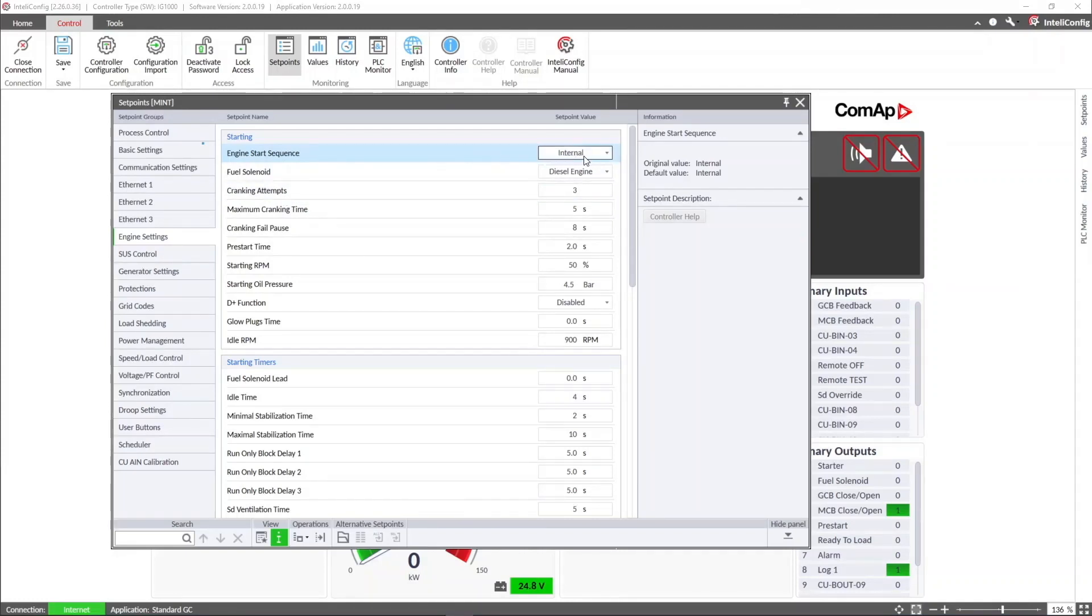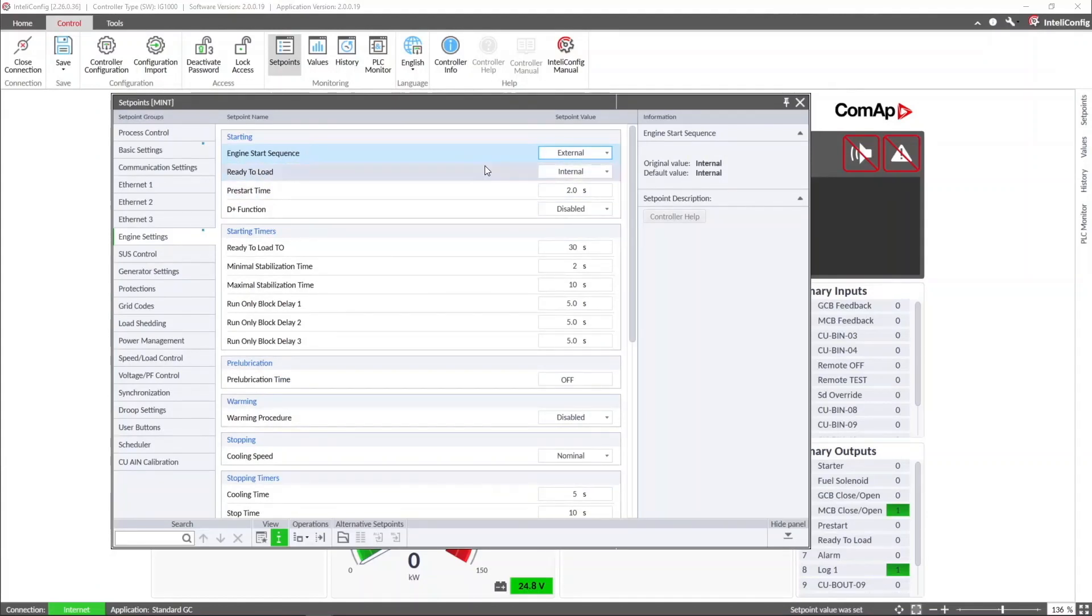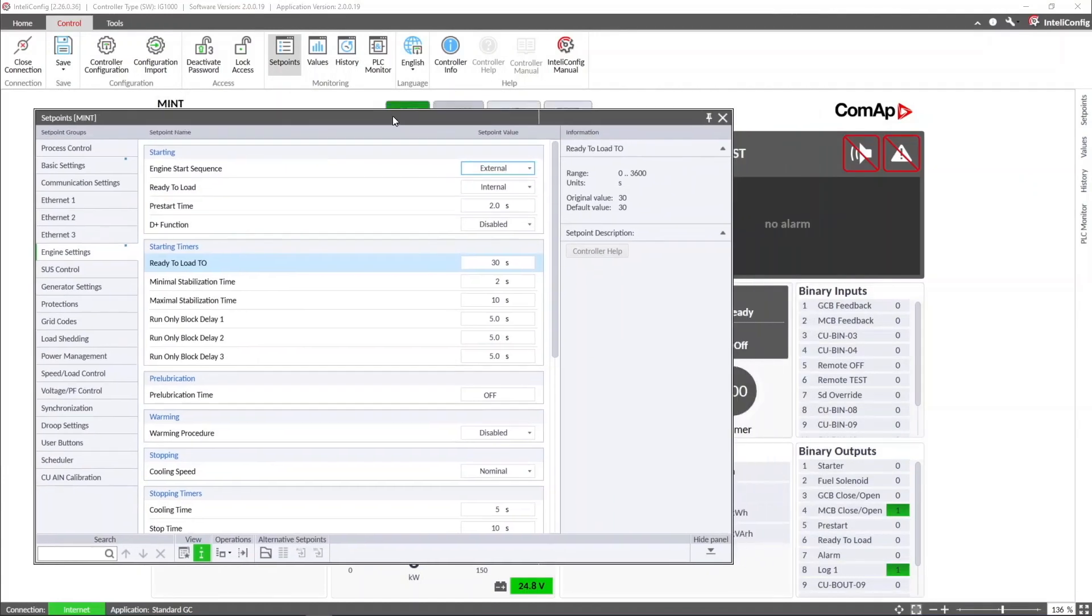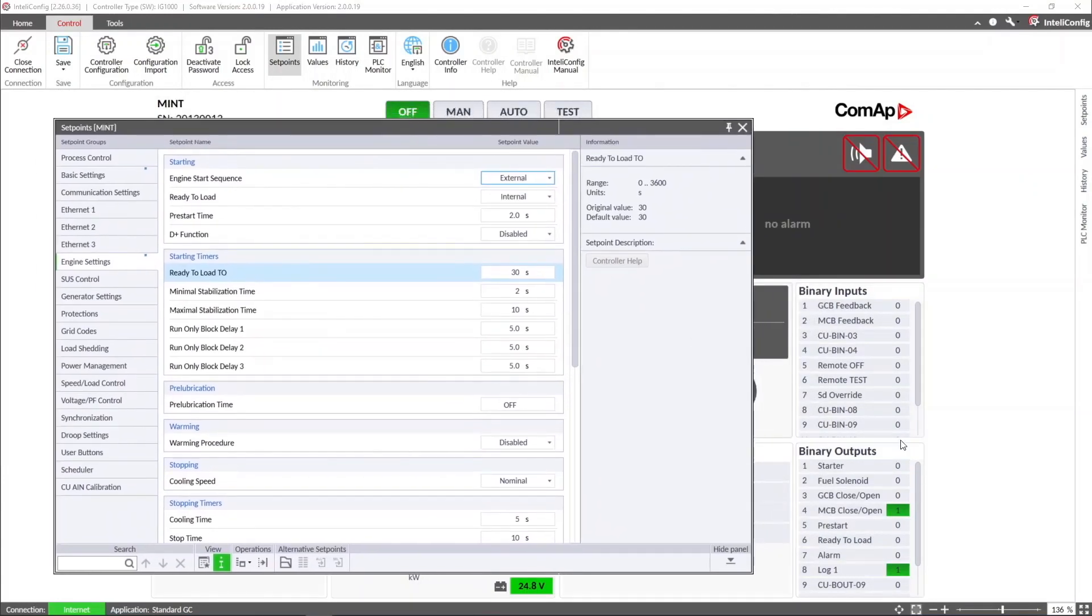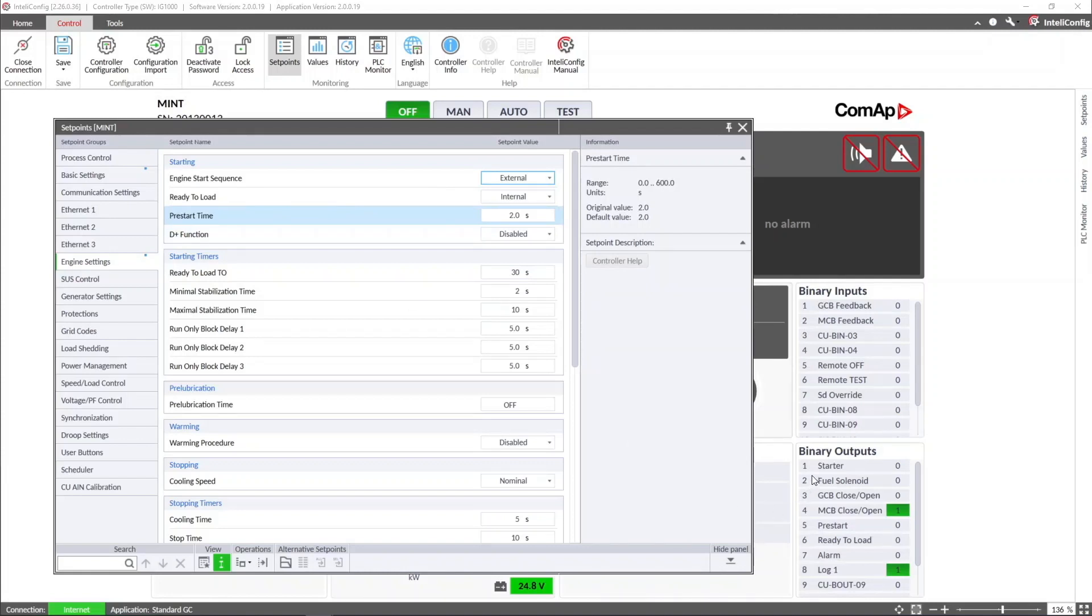The option external is the one that will let the controller know that the engine ECU or other control system will handle the engine start sequence. When selecting this option, the controller will not activate or control the starter output anymore. Once the controller receives a start command or a remote start stop signal depending on the controller mode, the controller will activate the prestart output during the prestart time, then it will activate the fuel solenoid output which must be connected to the remote start input in the ECU or in the engine control system that handles the start sequence.